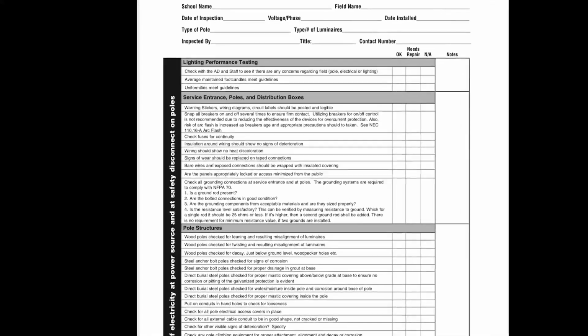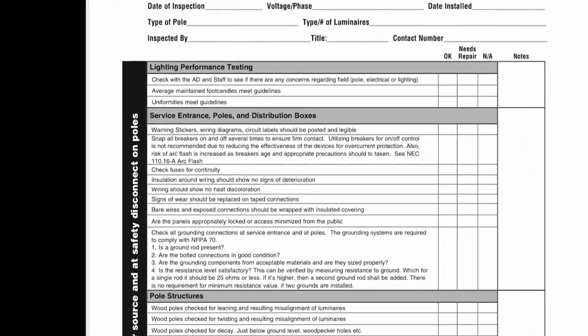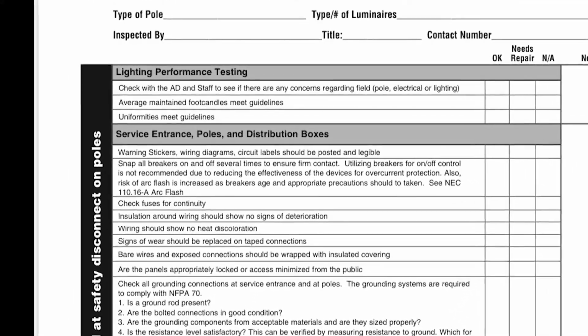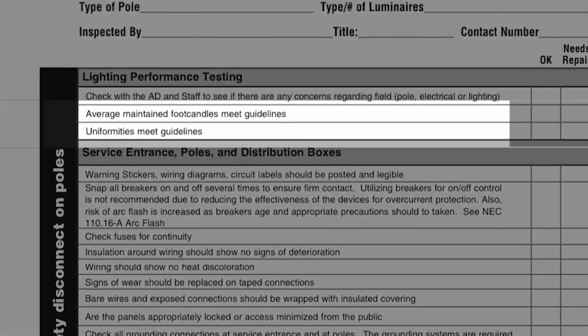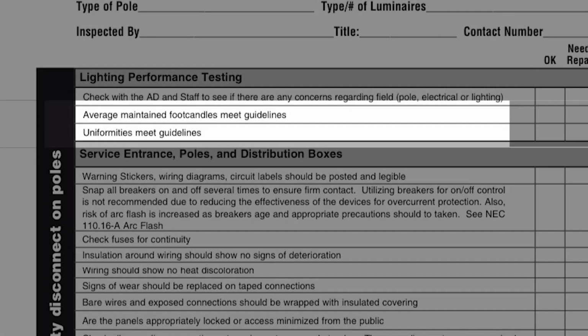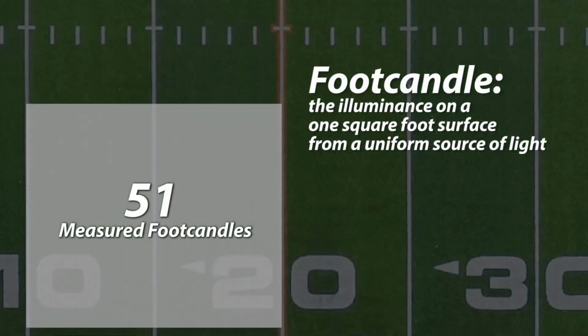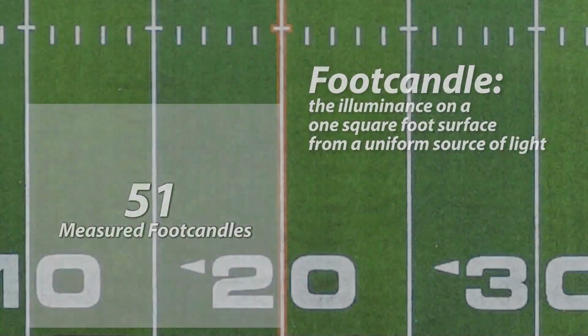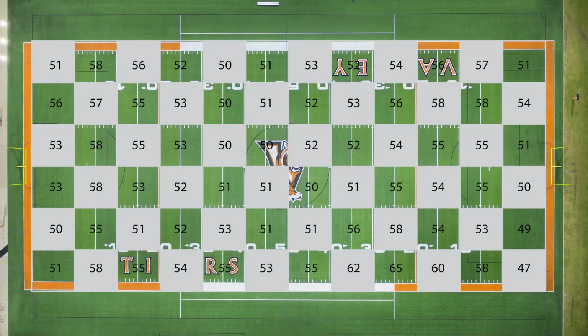When it comes to testing your system's on-field lighting performance, the goal is to ensure that it's meeting North Carolina High School Athletic Association standards in terms of quantity and quality. Quantity of light refers to the light levels, which are determined by the units of measurement called foot candles that are being achieved across the field. Quality of light refers to uniformity, which can be determined by comparing the number of foot candles in one area to the number in adjacent areas and the overall smoothness of light distribution.